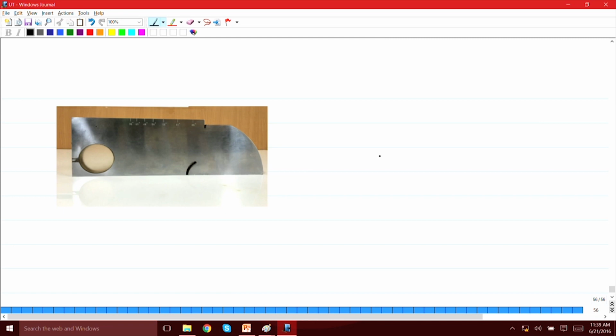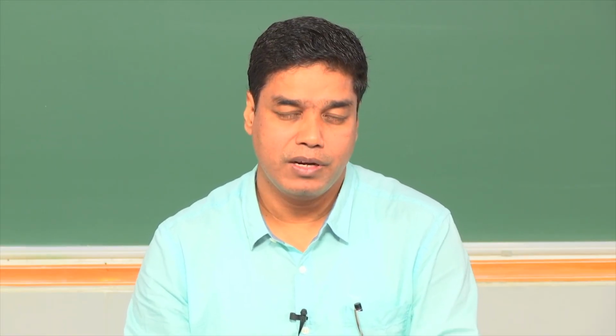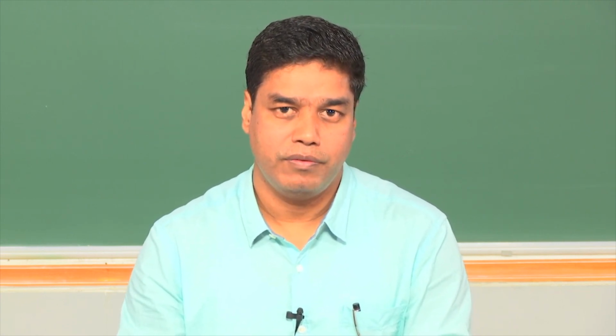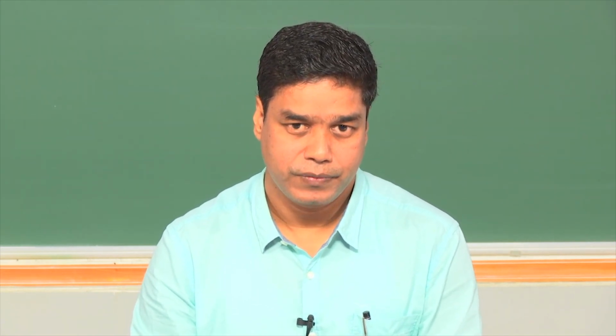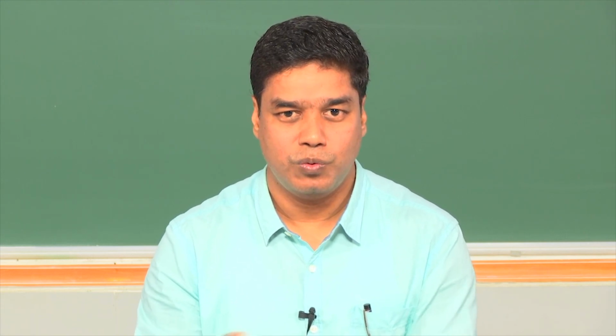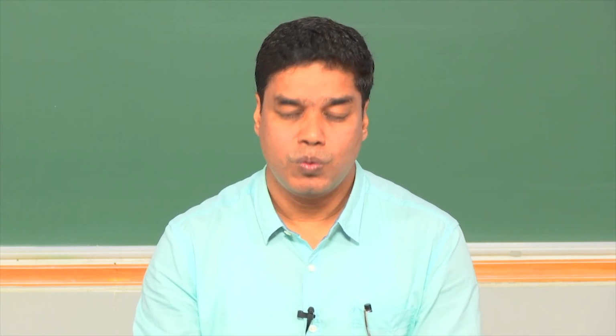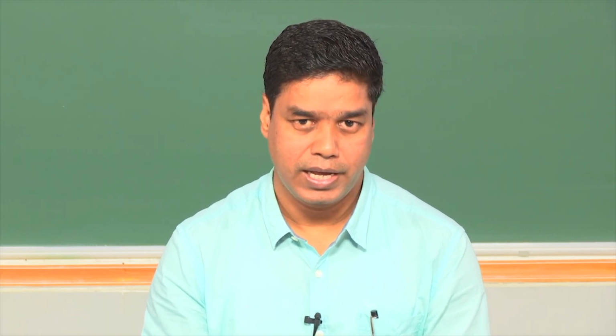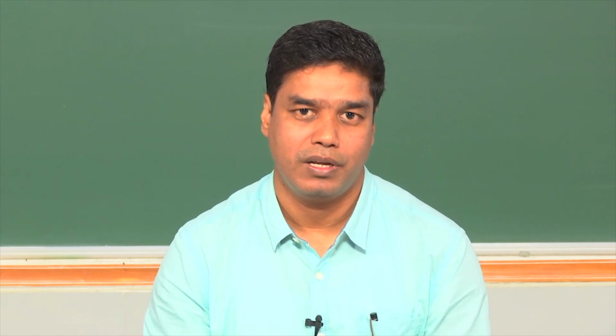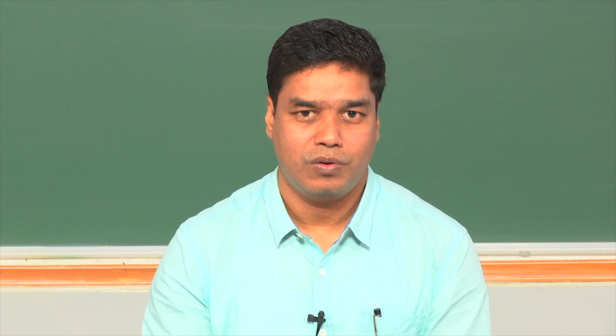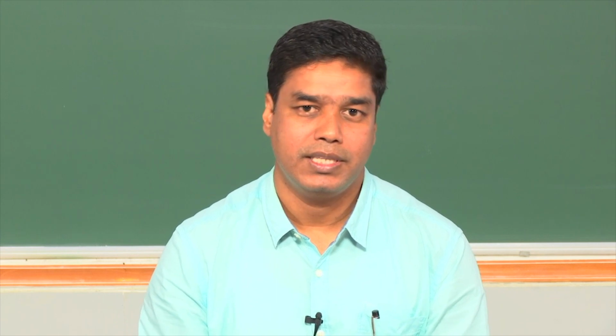We will see one more important thing which can be found by this IIW block, which is the resolution of any ultrasonic probe. Resolution means that if you have two closely spaced defects lying very close to each other, then you should be able to get two different echoes from these defects, instead of getting a single peak or two peaks merged together into one. If you get two separate echoes from these two defects lying very close to each other, then you say that the resolution of that particular probe is good. On the other hand, if you do not get two separate echoes, then you say that the resolution is not good.